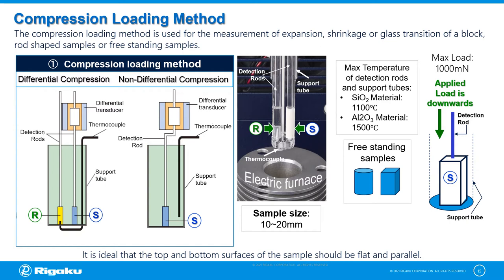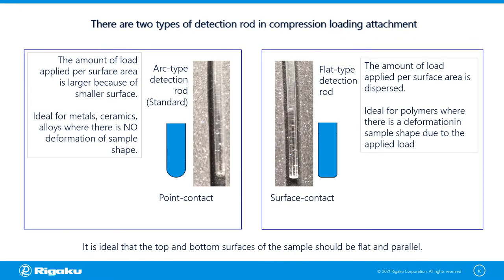When performing measurements, it is ideal that the top and bottom of the sample should be flat and parallel. In the compression loading attachment, there are two types of detection rods. The arc-type detection rod is standard; the amount of load applied per surface is larger because of a smaller contact surface, making it ideal for metals, ceramics, and alloys where there is no deformation of sample shape. On the other hand, the flat type detection rod is ideal for materials such as polymers where there is deformation of sample shape due to the applied load, as it disperses the load per surface area.